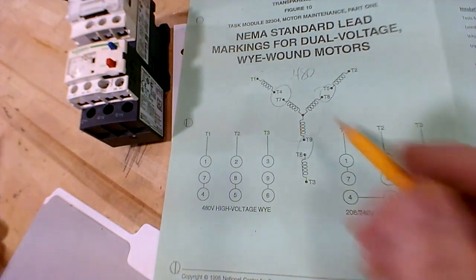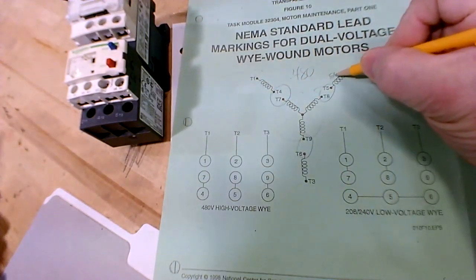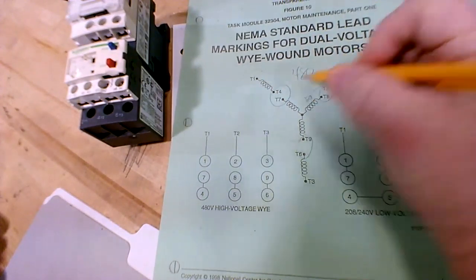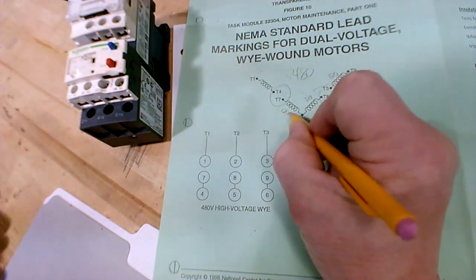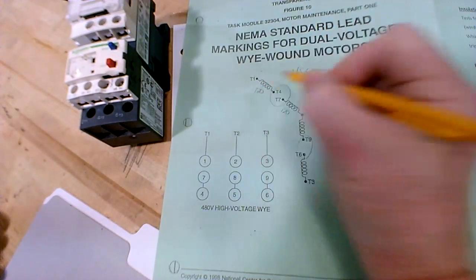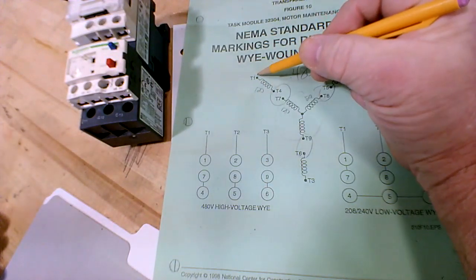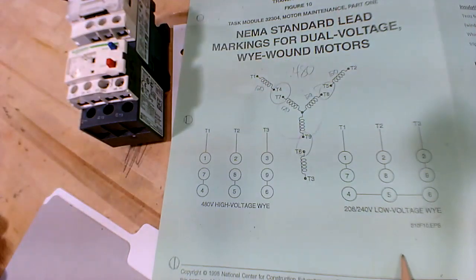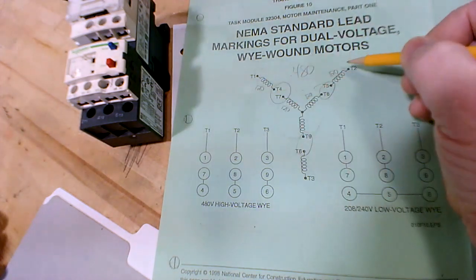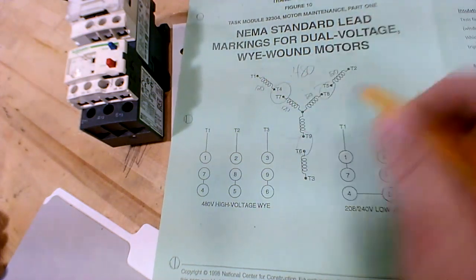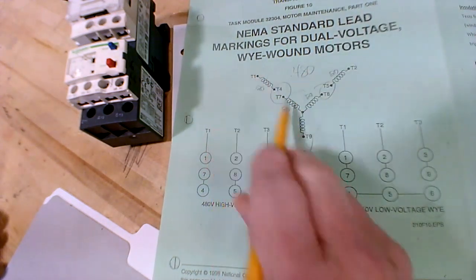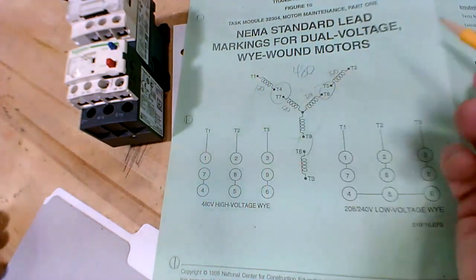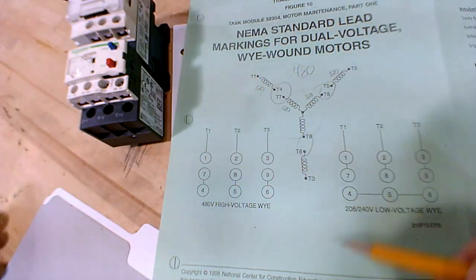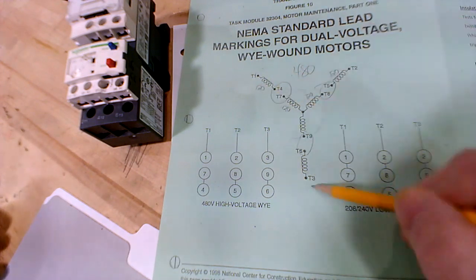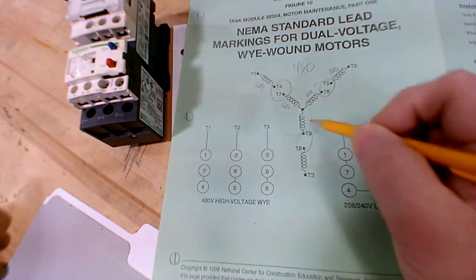120. So you will measure 120 across this one. You'll measure 120 across that one and 120 across that one. Seriously, if you put your probes in there, that's what you get in the motor. You get about 120 across each one individually in series. Or if you measure here to here, you would measure the 240. So each winding is getting about 120 a piece in this case, and the same thing here. If you measure across here, same thing.